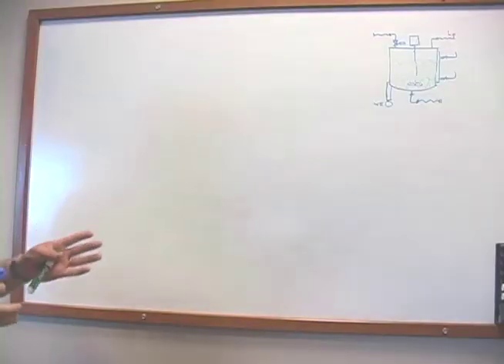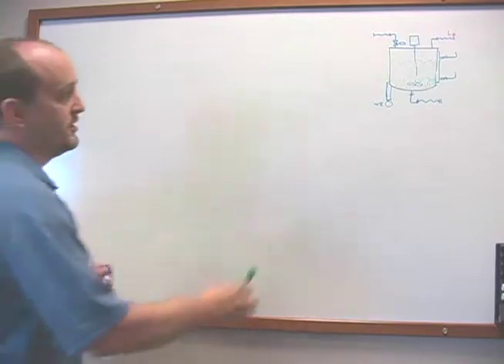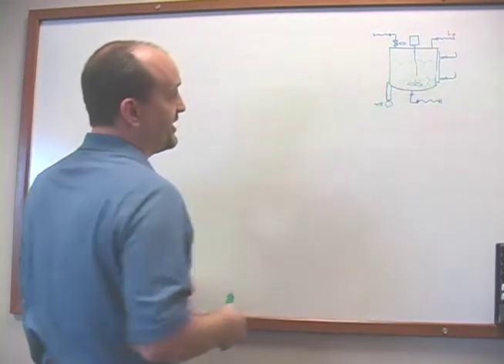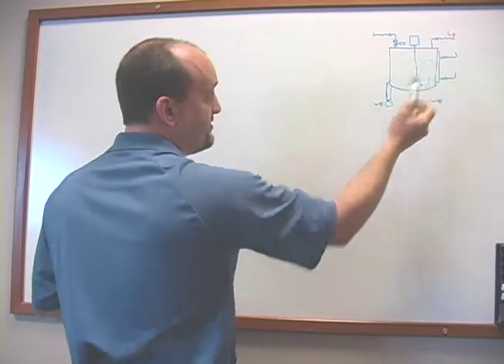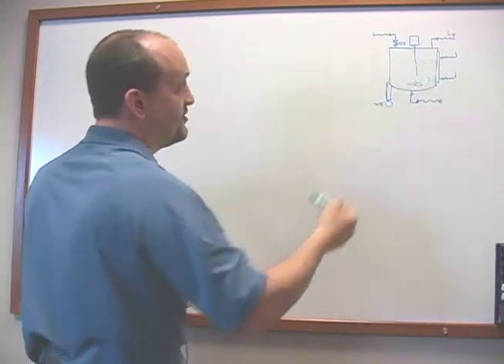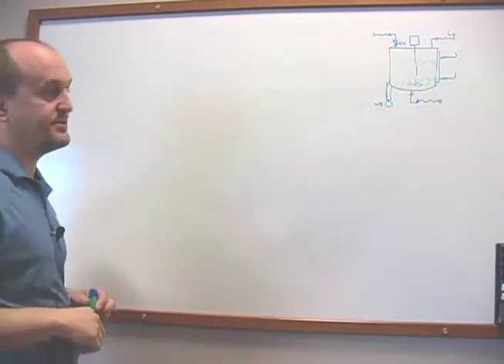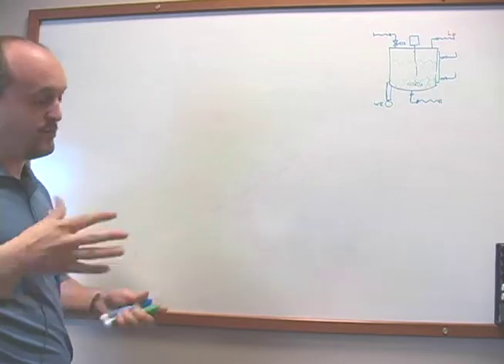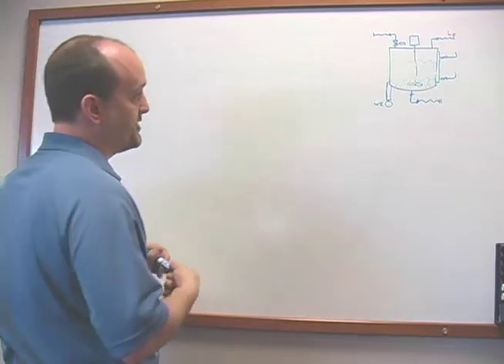Now let's talk about why we zero and why we calibrate. If this is your load cell on your tank, your tank has weight. It's made of metal. You have agitators. You have static loads. It's set on those load cells. You don't want to measure those. So you want to zero those out. That's why we zero.